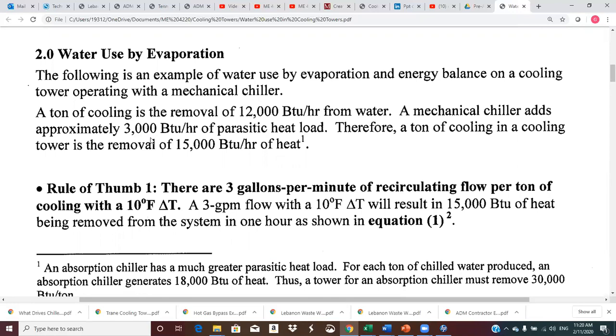3,412 BTUs per hour. So we're saying if it's a kW per ton, we get about 3,000 BTUs an hour of energy added to the refrigerant in the compressor that has to be cooled away by the condenser water. So thus, for every ton of cooling in the evaporator, the condenser actually has to reject 15,000 BTUs of heat. So a cooling tower ton is 15,000 BTUs per hour on a centrifugal or reciprocating chiller.